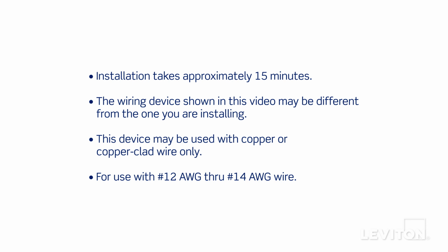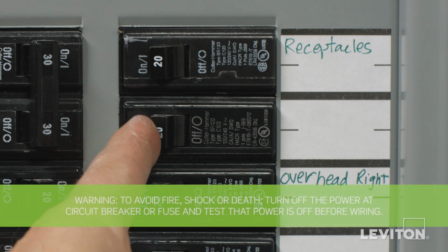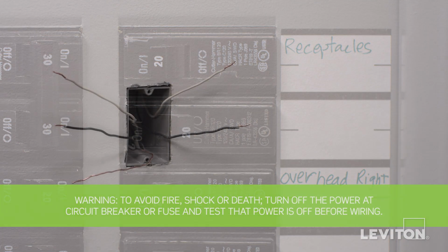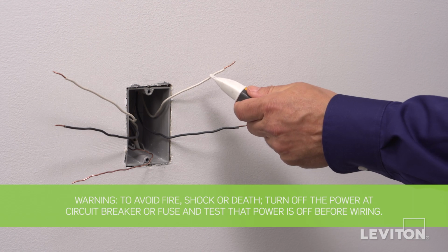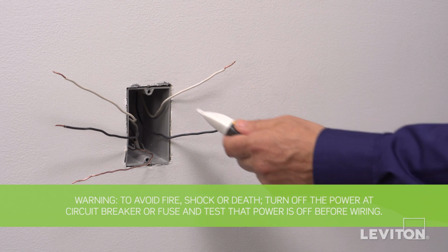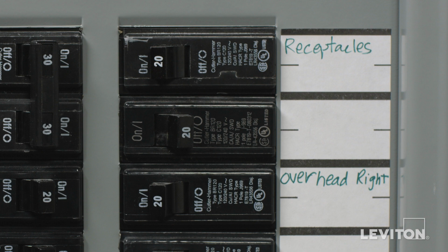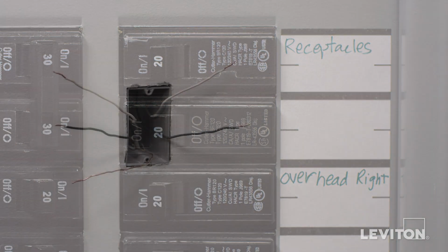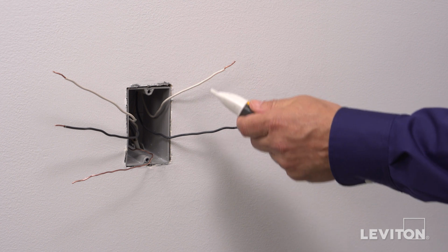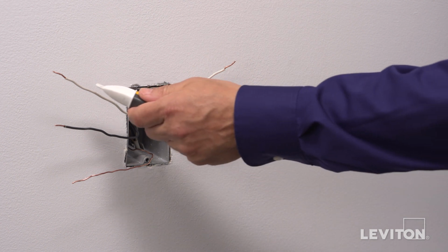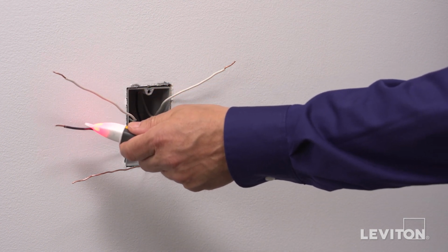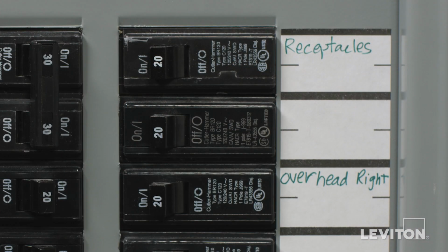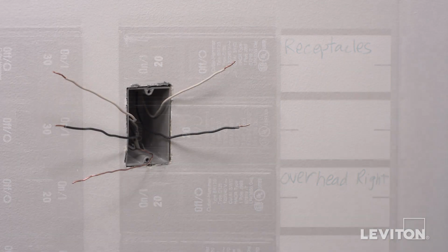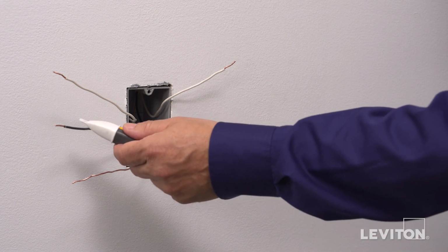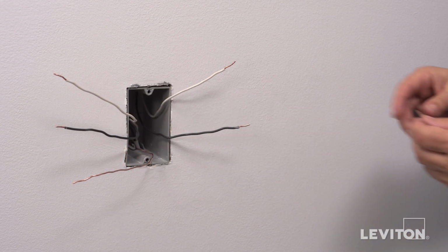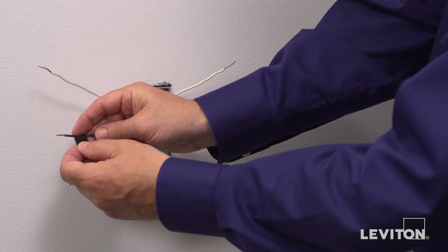Local codes take precedence. Be sure to turn the power off at the circuit breaker and use a voltage tester to ensure that the power is completely off. Now, we need to identify the hot wire. To do this, turn the circuit breaker back on. Carefully use the voltage tester to test each wire. The hot wire will be indicated by the tester. Once identified, turn off the circuit breaker to shut power and test to ensure that the power is off. Use a small piece of electrical tape to label the hot wire.